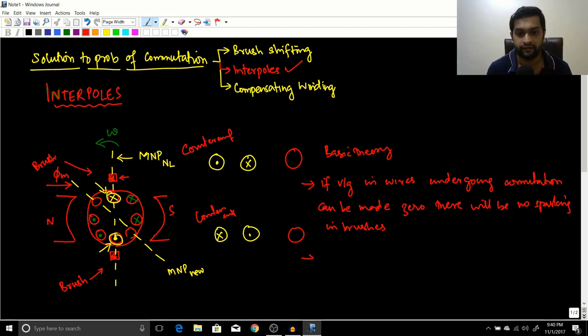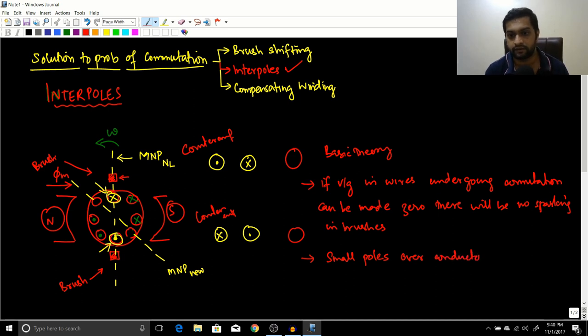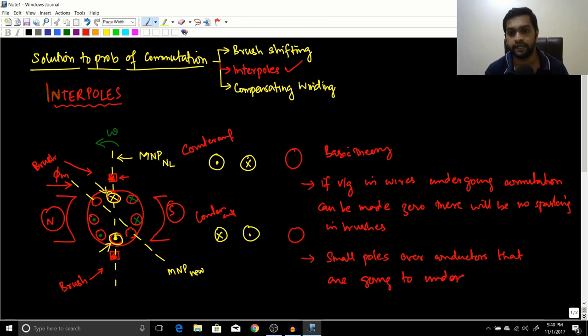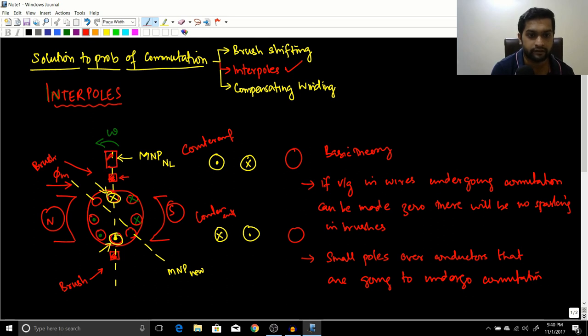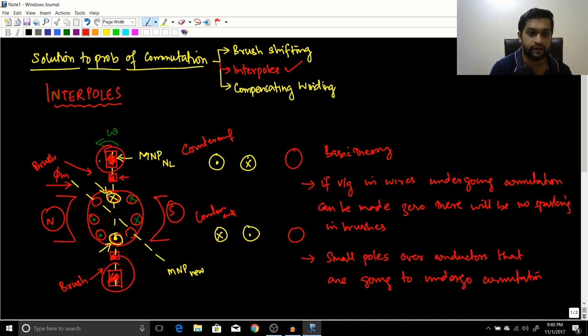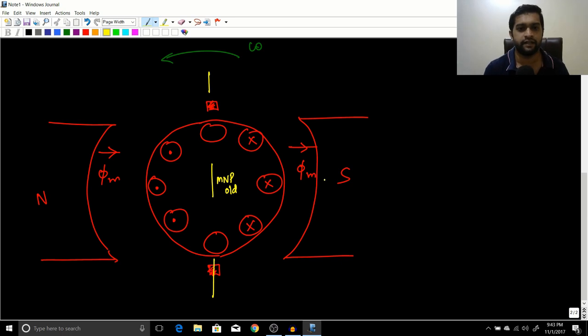What we do is place small poles — similar to the main north and south poles — over the conductors that are going to undergo commutation. We make a small pole here and a small pole here, such that when the conductor rotates past this pole, it gets a counter EMF on that conductor, cancelling the unwanted EMF. That is the solution provided by the interpoles.